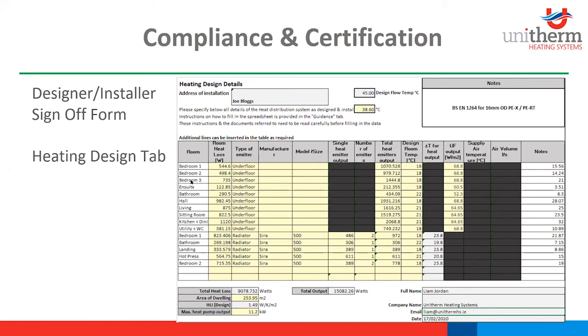Then we have a heating design tab. It's completed for the BER assessor along with the SR50 heat calculation. So as you can see here, we have rads present. So when there's rads present, we do a full SR50 heat loss calculation for the BER assessor and the engineer involved. It gives the total heat loss for the building, the total heat output of emitters installed, and the design heat loss indicator. So you can see in that building the HLI was 1.49 for a 253 square meter building.